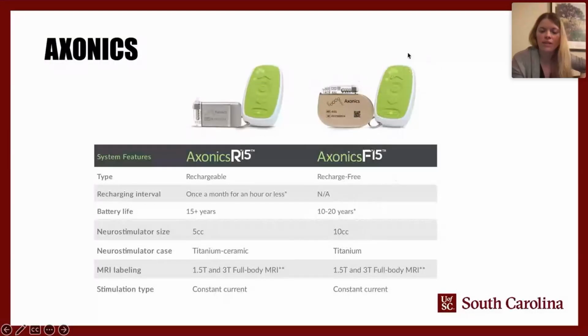The remote for the Axonics device is also different from the competitor Medtronic, and I'll show you that. They chose to go with a much simpler remote. This remote has 2 programs available on it, and really all the patient can do is change between those 2 programs and increase or decrease their amplitude. And this device does not require another communicator. This device communicates directly with their program without having to put anything over top of the skin to communicate with the device in the remote. So that's one of the advantages that some people like about this, it's a kind of key fob, is what they call it, an easy device to manipulate with no communicator or third piece needed.